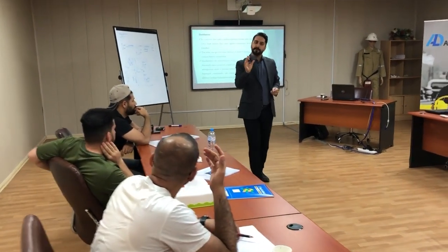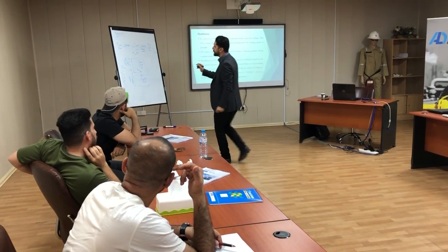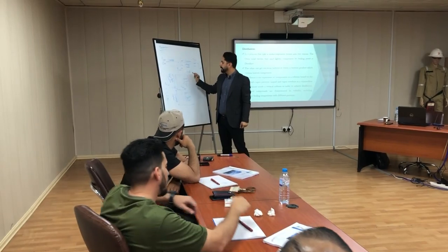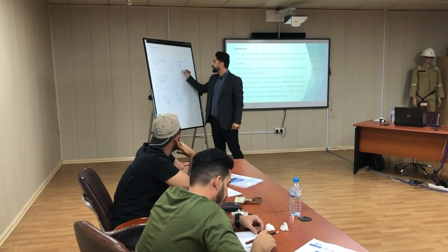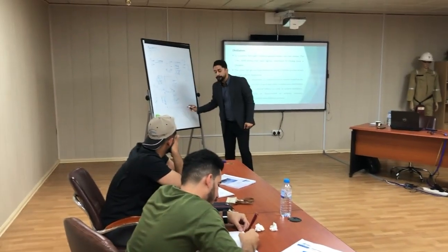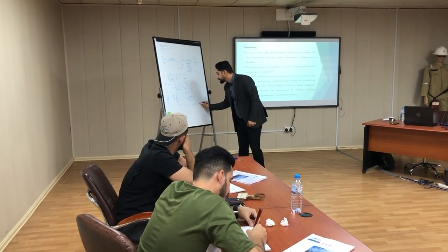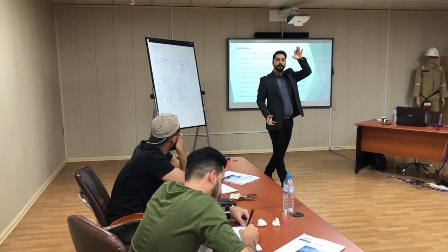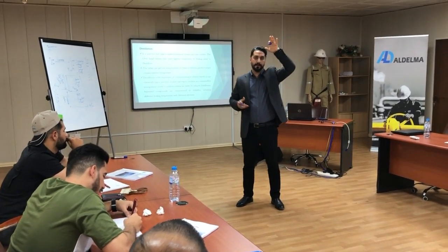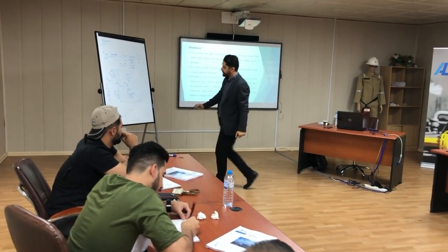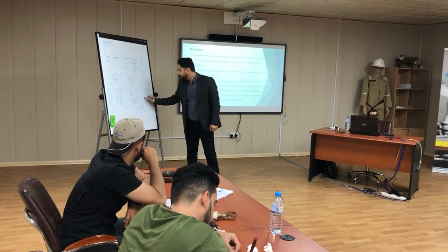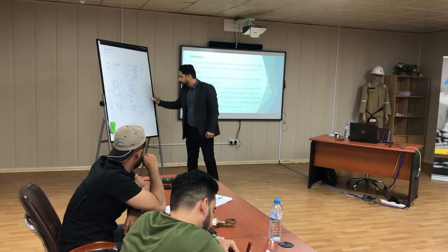Yes, but even in the cryogenic method, for example, in a demethanizer, I should reach a temperature of minus 90 and the pressure would be about 30 bar at the top, and the temperature at the bottom would be about 40 degrees Celsius. There should be a temperature difference from top to bottom. So always, for achieving this temperature at the bottom, I will need a reboiler.